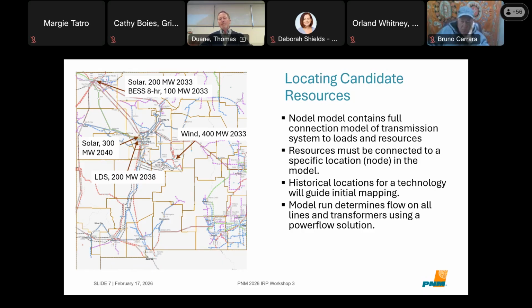Model runs determine flows on all lines and transformers using a power flow solution. If flow exceeds path limits, which can be defined as basically interfaces of multiple lines, or exceeds individual line or transformer limits, the model redispatches the resource to relieve those limits. The redispatch comes at a cost that requires resources be dispatched out of economic order.